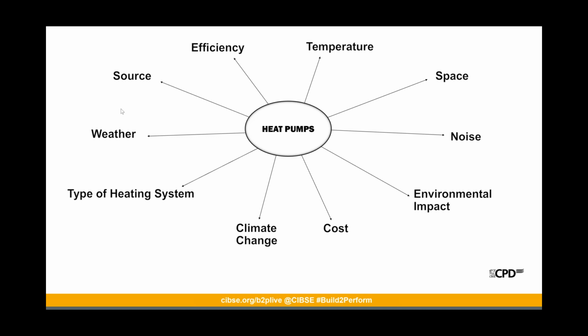Temperatures are also important, as we have to determine what type of heating system. For example, radiators would be more difficult as they run at higher temperatures. We also have to take into consideration the available space, not only for maintenance, but for air movement to mitigate the creation of microclimate conditions and ensure correct functioning of heat pumps. When deciding the location of the heat pumps, we have to consider the acoustics, the impact on neighbors, and how we can mitigate noise issues.